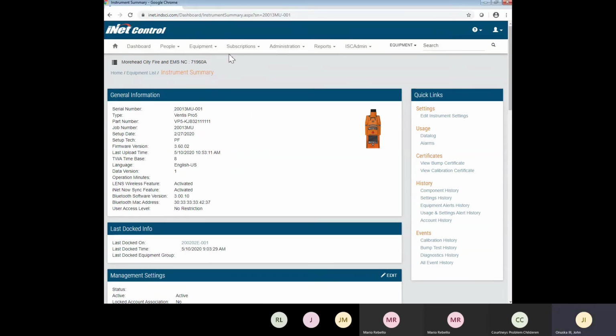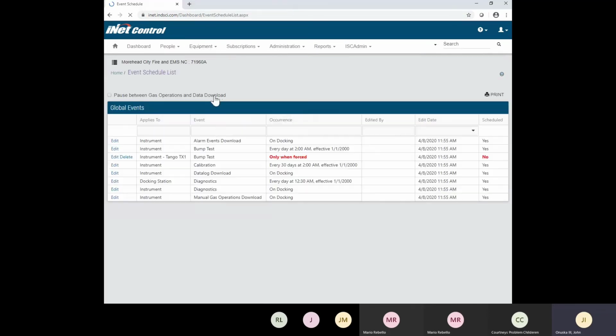All right. And then the other thing I wanted to show you on here is up here at the top under equipment. If we go to event schedule, this is where it does the bump tests and calibrations, and it does it based off of this schedule right here. So here's that bump test I was telling you. Every day at 2 a.m.